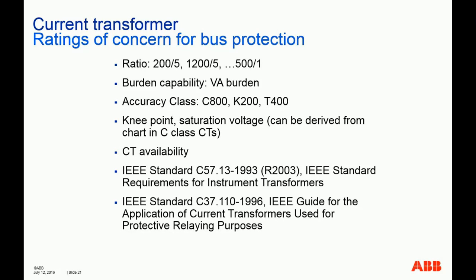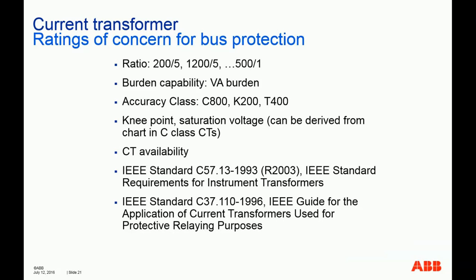So in other words, for the C800 CT, that tells us that this CT can withstand 800 volts across its burden, its rated burden, with 20 times the rated current. For the 5 amp CT, that will be 100 amps without exceeding 10% measurement errors. Okay.